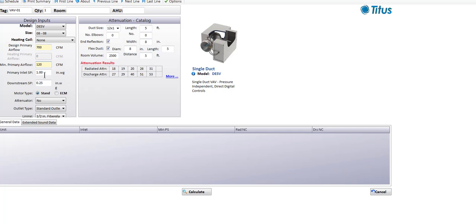On the screen there's the primary inlet static pressure, which defaults to one inch — that's one inch water column pressure on the inlet duct. That's pretty standard in VAV systems today. If this box is going to have water coils on it, we might need more than an inch of static pressure, but one inch is a pretty good default.